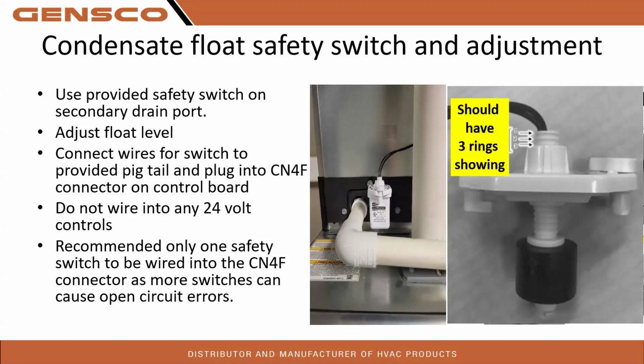If you have another switch that you want to put on there, like a pan switch or condensate pump, something like that, I would recommend using that to break your 24-volt controls on your furnace. It won't shut the coil down right away, but the coil will shut down on coil thermistor errors once the fan stops running on that thing. So it will shut the system down eventually.